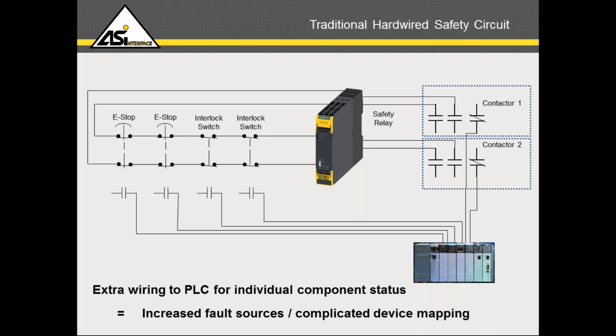In addition to the safety circuit wiring, to monitor those circuits, you'd also have to run additional wiring back to a PLC or some other control device, and you also have to map all the inputs into the PLC, and that creates additional labor costs, obviously. I also want to emphasize that the additional wiring associated with the hardwired safety circuit creates additional costs. All that wire itself is an additional cost, but also those wires have to be run either in conduit or cable trays, so there's another cost.